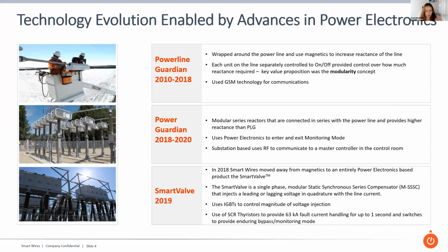So you can bypass at a modular level or at a converter level, and that's really good for not having a single point of failure. So if you do have a problem with the valve, you don't lose your whole installation, you lose a percentage of your installation. It's one of the benefits of modularity. I hope that answers the question. Yes, thank you.